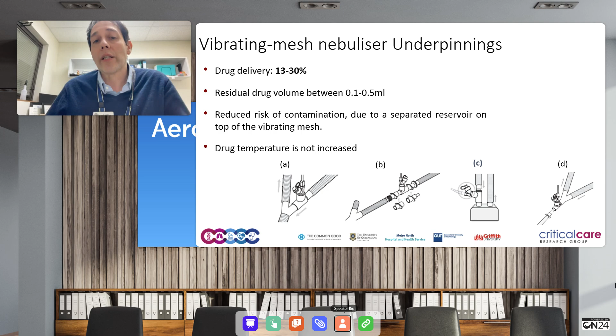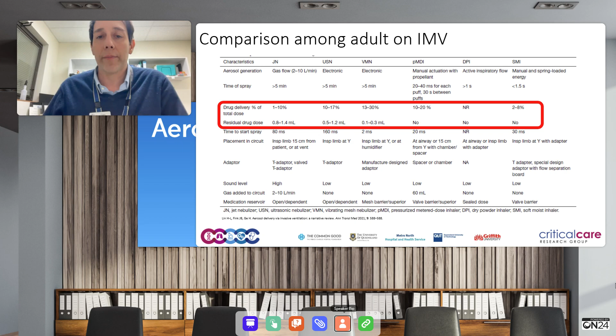Now, in terms of comparison with other devices, this is a slide that I often present when I talk about aerosolization. Look, for instance, at the jet nebulizers. They have a drug delivery of up to 10%. Ultrasonic nebulizer 17%, and MDI reaches up to 20%. But this clearly tells you two things. First of all, that there's been a revolution with the vibrating mesh, but still, of the drug that you are trying to deliver, just a minimal part is actually delivered.